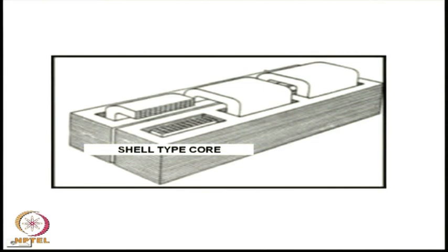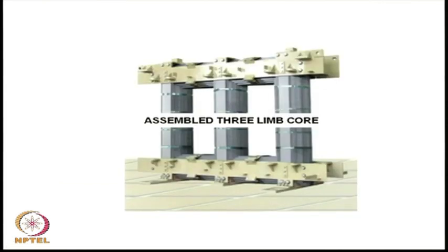So, here is a look at the assembled three limb core. There are several parts to it. These vertical parts are called the core, the horizontal one is called the yoke. As in the case of a single phase transformer, these are not solid iron bars. They are made up of thin steel laminations. The purpose of the core is similar to that of a single phase transformer, that is to provide a low reluctance path for the flux as well as to support the winding and provide mechanical strength.